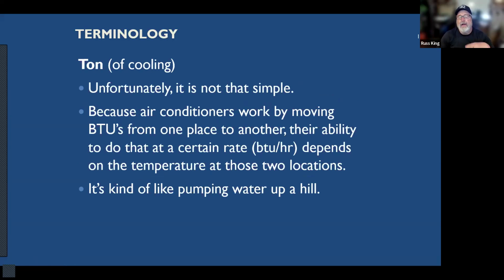Air conditioners, the actual capacity that it gives you depends on the conditions that it's operating at. Unlike furnaces, furnaces are dumb beasts. They make flame and they give off heat, okay? Very little will affect the capacity of a furnace. The only real thing that affects the capacity of the furnace is if you go really high up in altitude, because then the air gets thinner, there's less oxygen, and so you have to start derating the capacity of the furnace. But other than that, it just gives off heat and off it goes. Whereas an air conditioner is very susceptible to a lot of different things. The outdoor temperature, the indoor humidity, the airflow, and all this other stuff.